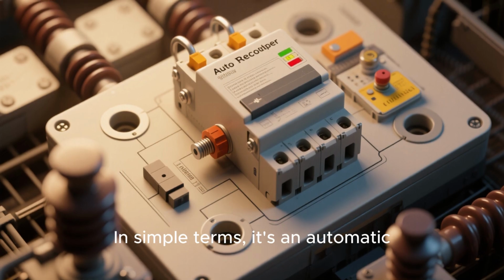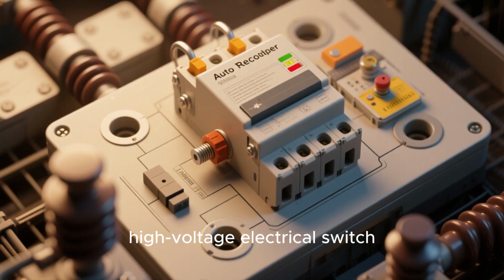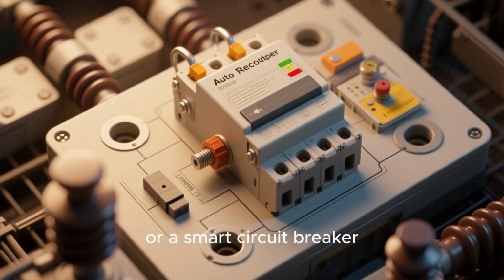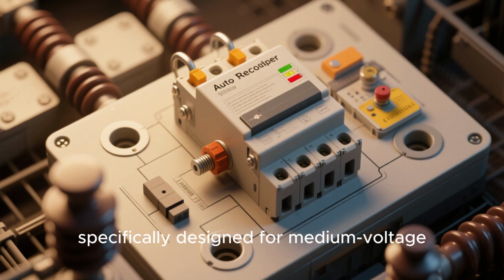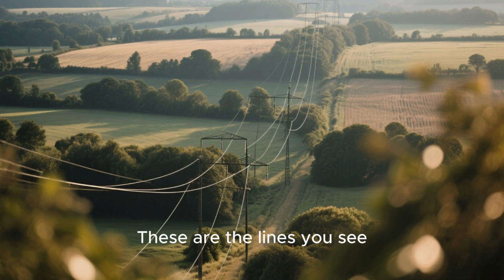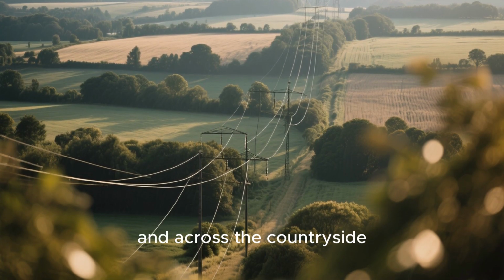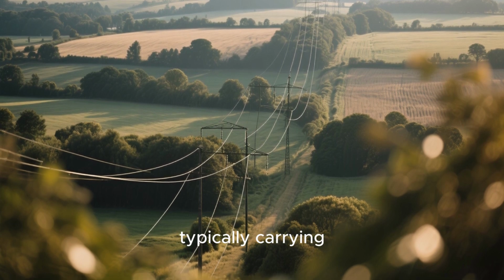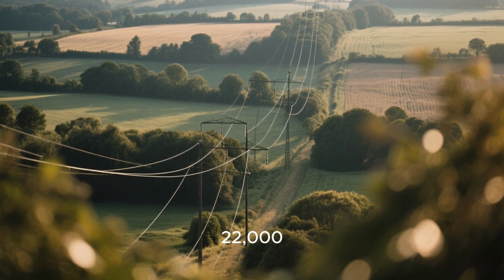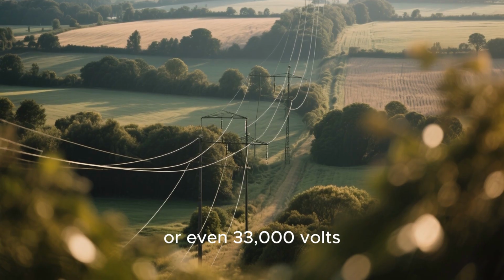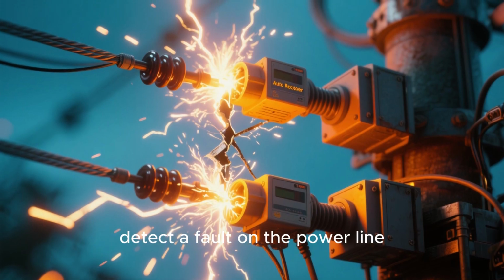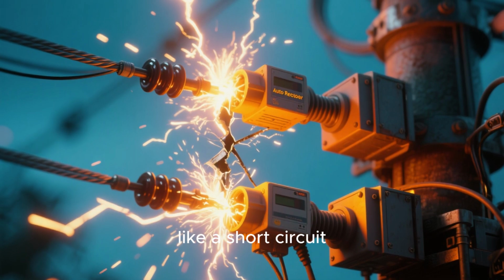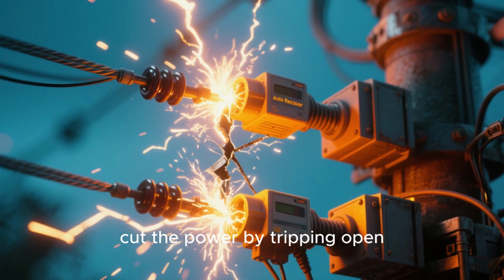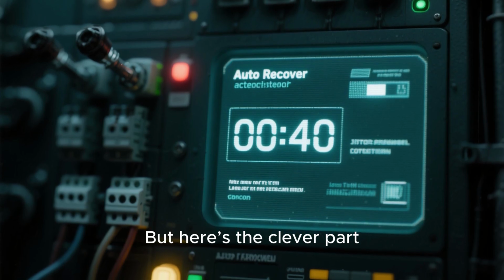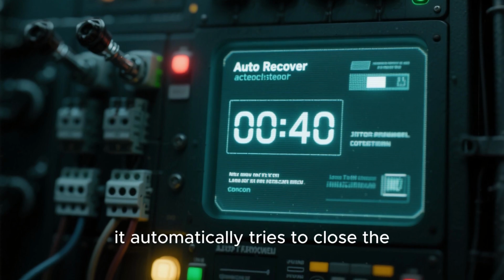In simple terms, it's an automatic, high-voltage electrical switch or a smart circuit breaker, specifically designed for medium-voltage overhead power lines. These are the lines you see running along streets and across the countryside, typically carrying 11,000, 22,000, or even 33,000 volts. Its main job is to detect a fault on the power line, like a short circuit, and then instantly cut the power by tripping open. But here's the clever part. After a preset amount of time, it automatically tries to close the circuit again to restore power.